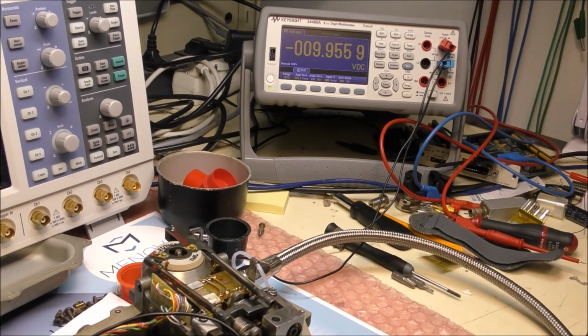I have connected the DMM at the output of this transducer, and as you can see, there is a voltage of minus 10 volts approximately when there is no input pressure. I have also connected the input pressure to a pressure generator here. Currently the pressure is 0. If I increase the pressure, you see that the voltage decreases. There is a leakage also, but this is another problem. The problem is this offset. There is maybe a problem with this transducer.